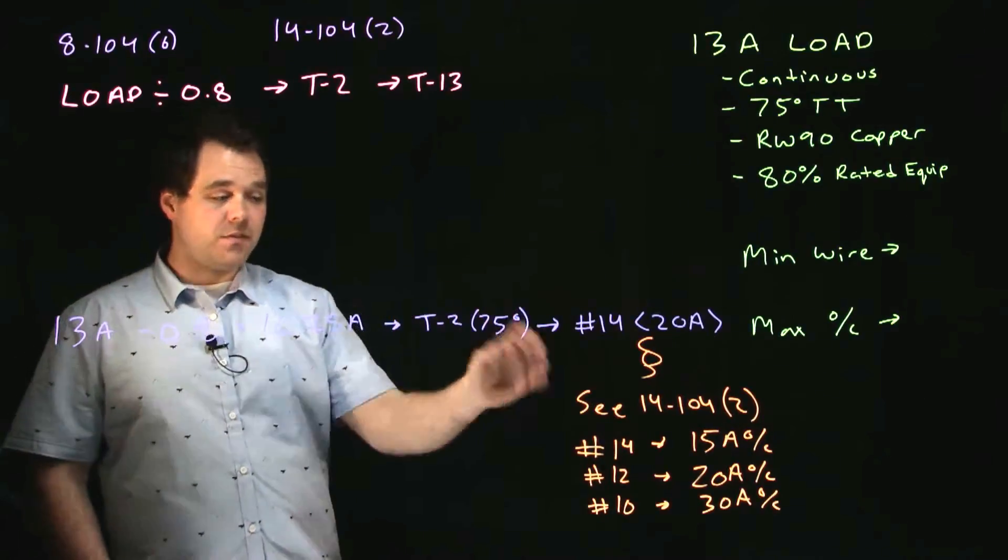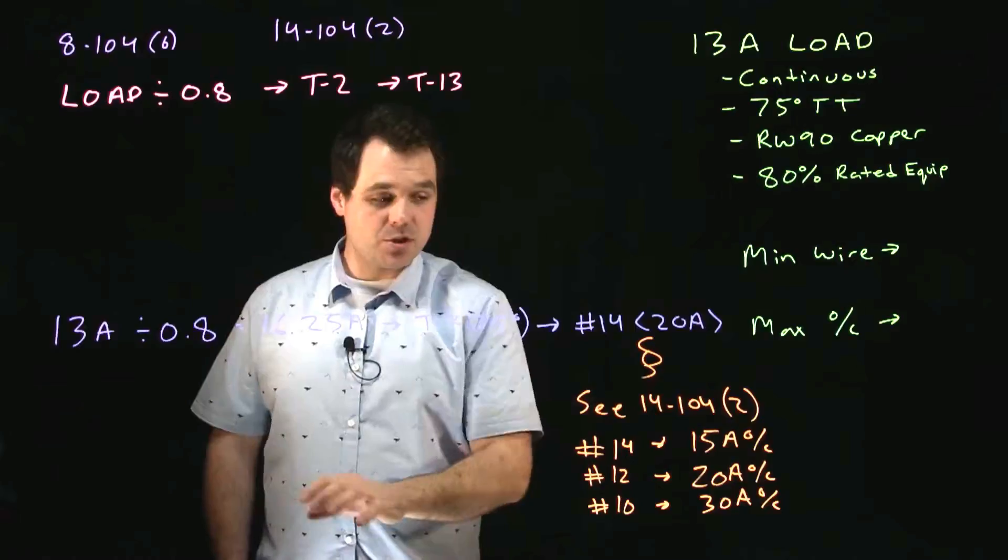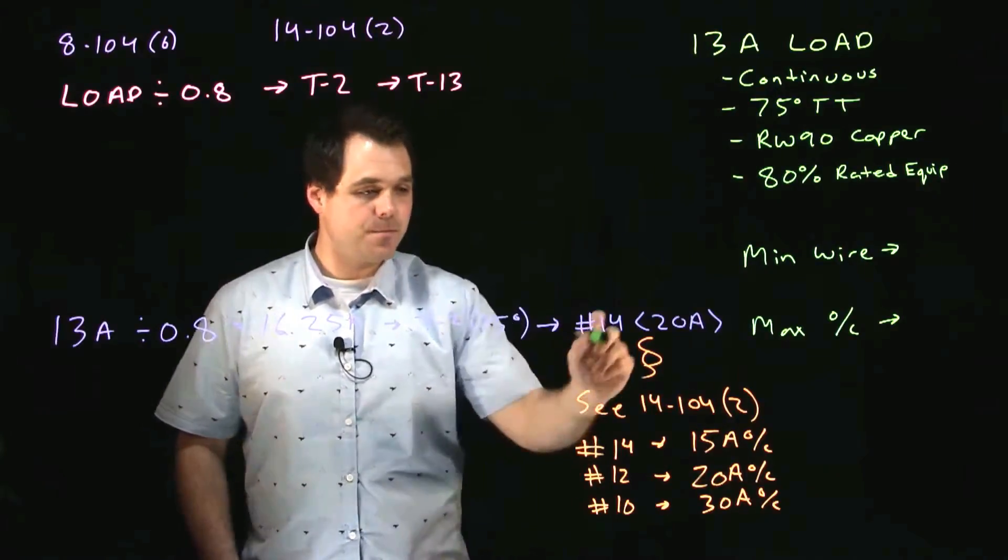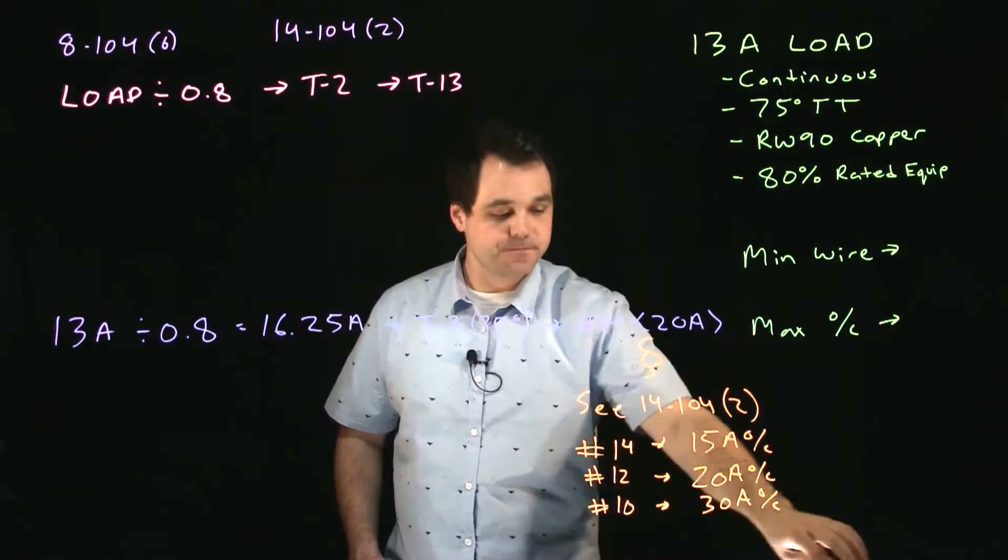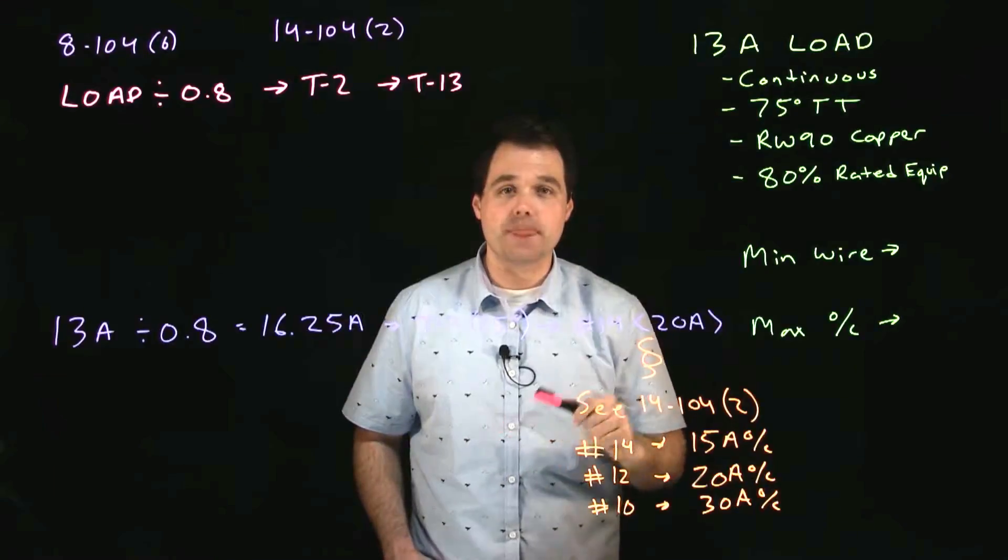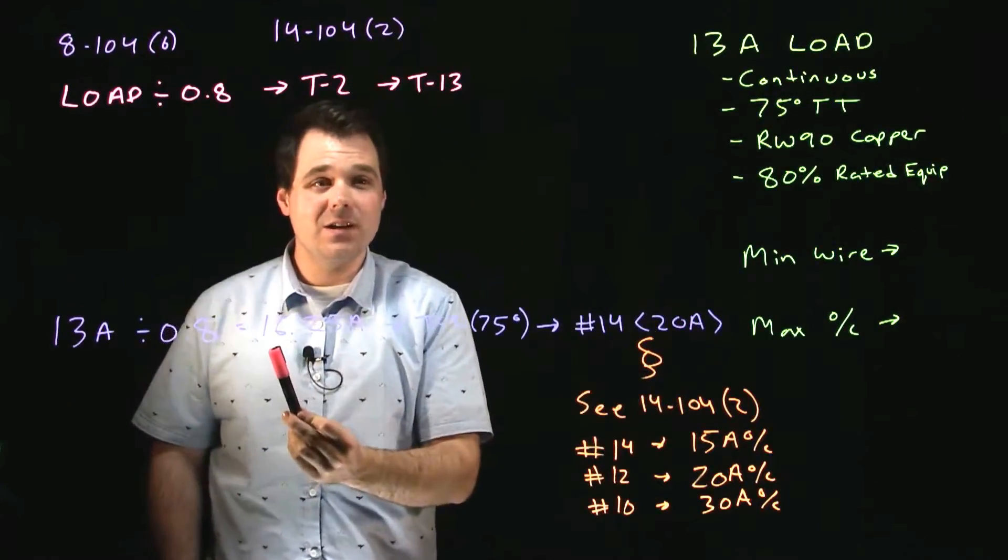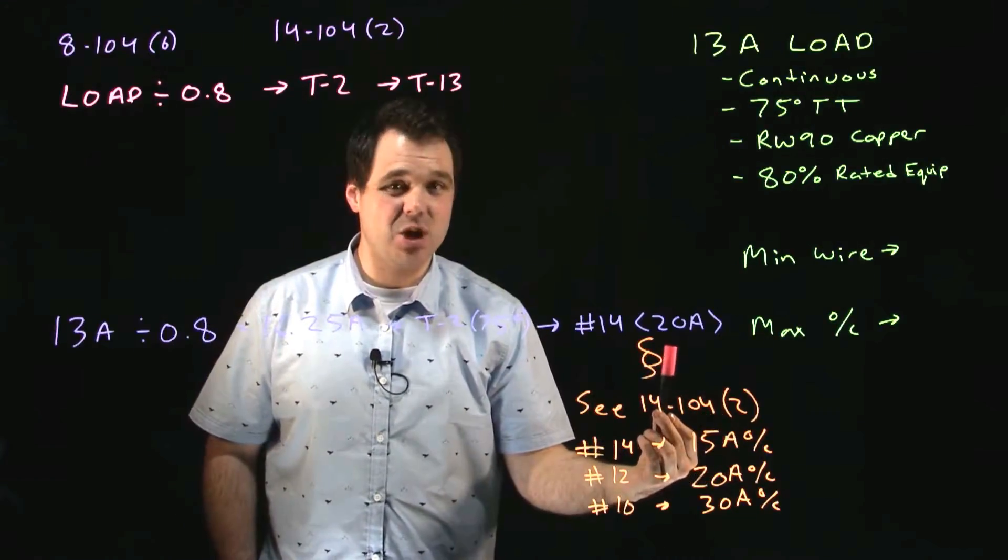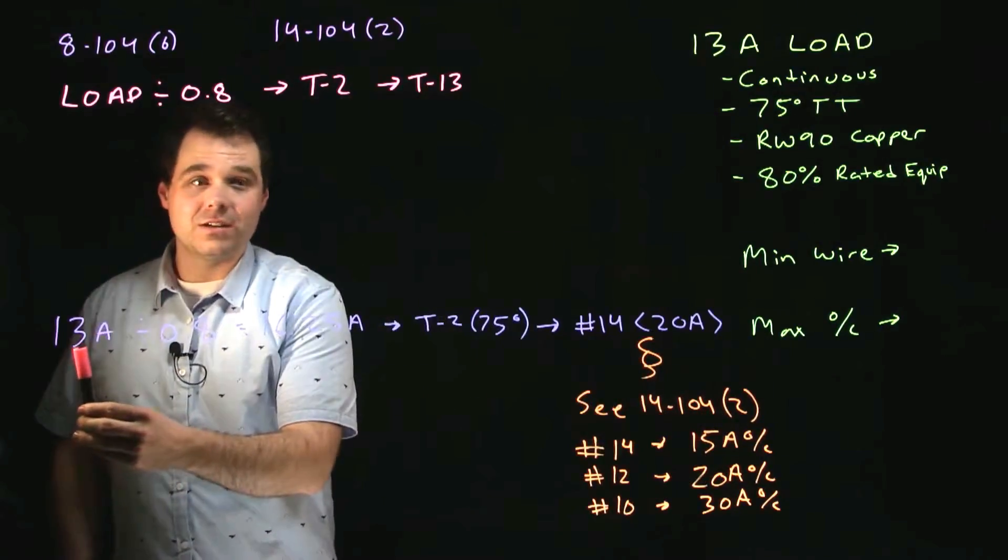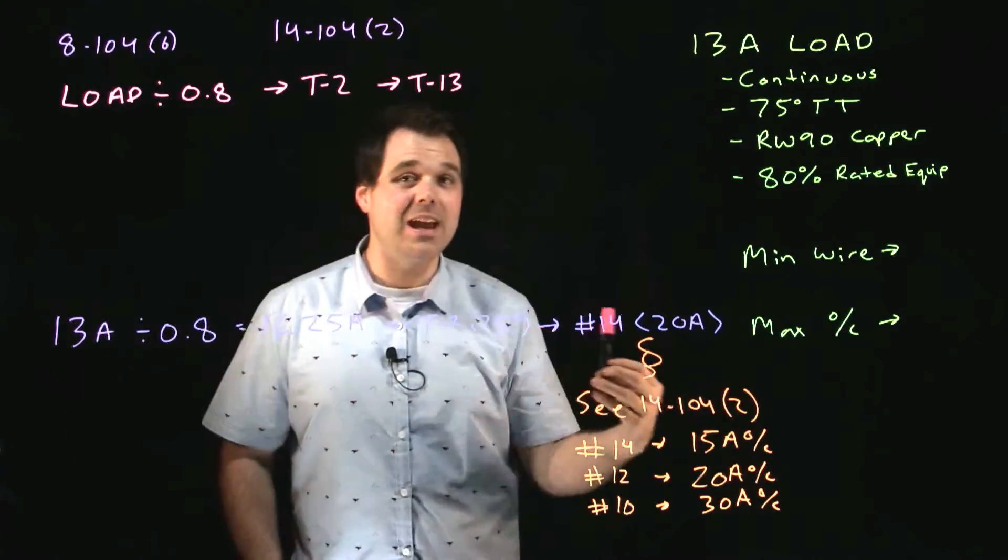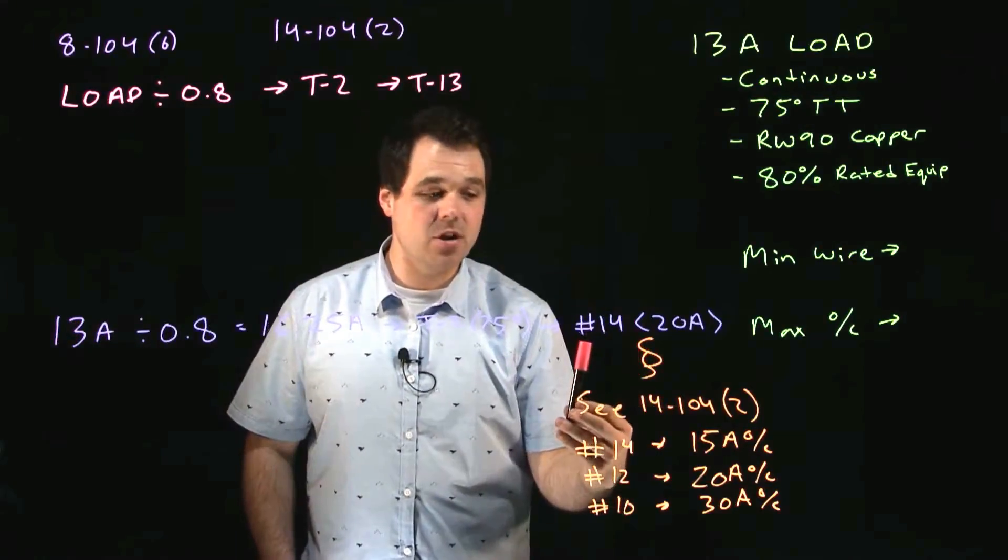If we were to put a 15 amp breaker on this number 14 which is what we are permitted to do by code, so we take our 14 gauge put on a 15 amp breaker. If we did that, 16.25 exceeds that 15 amp breaker. So that is not allowed. Or 13 amps exceeds 80% the rating of the breaker. So that is not allowed.